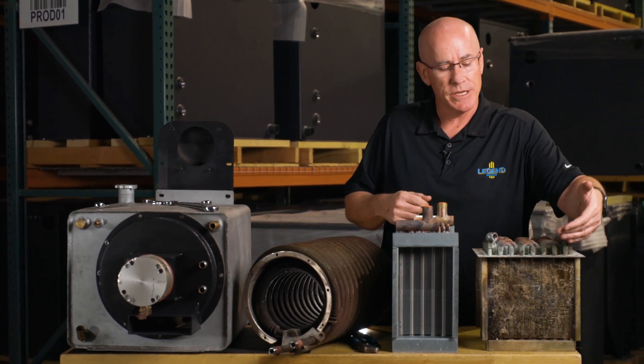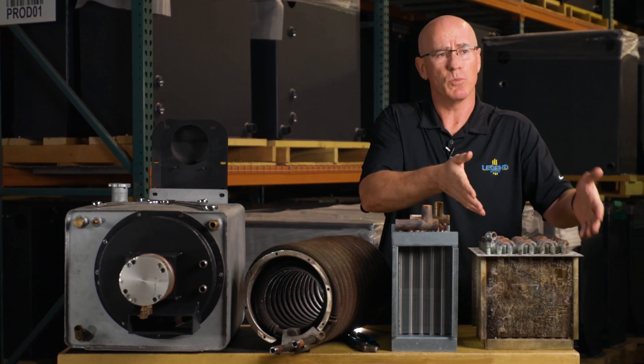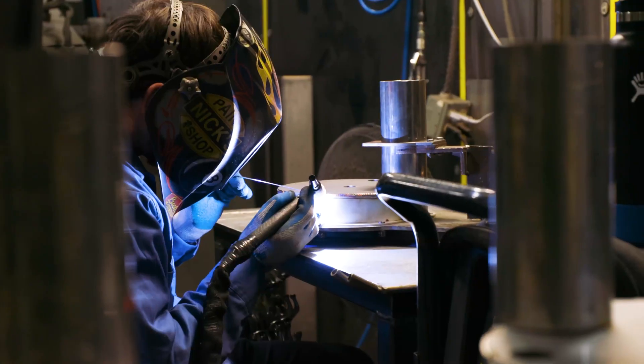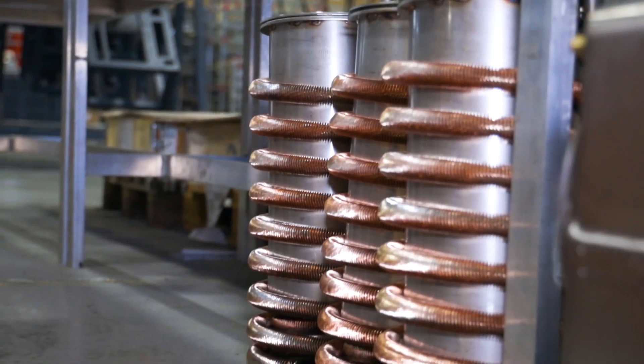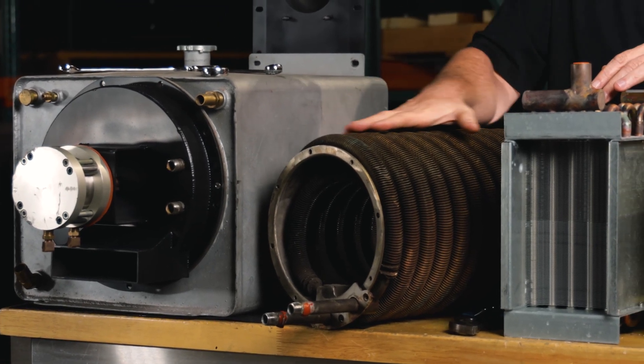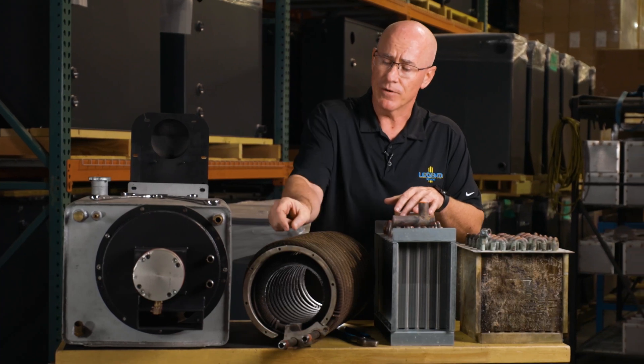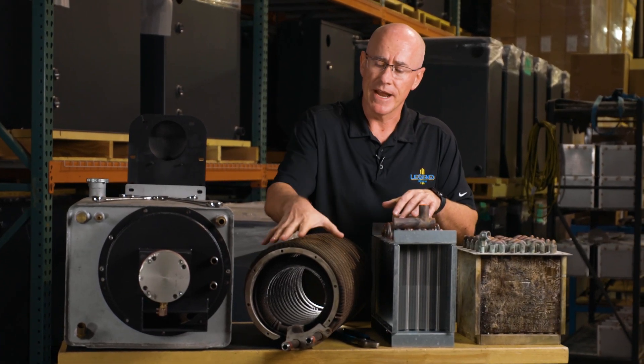A couple of challenges: it tends to plug up a little bit more easily and requires service more often. But what we've done at Legend Brands is we have created a coil style heat exchanger with copper fin tubing. What we're doing here is we've got, for example, a 60-foot length of stainless steel coil. For every one inch, there are 10 of these copper washers and it acts as a heat sink.